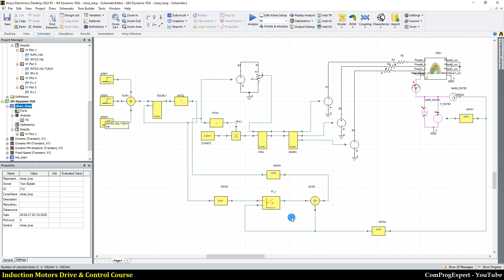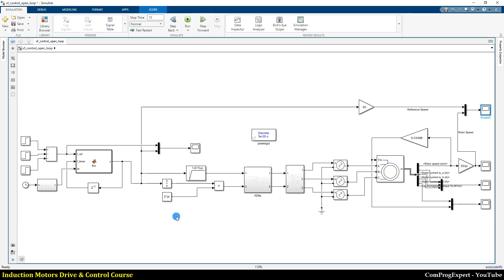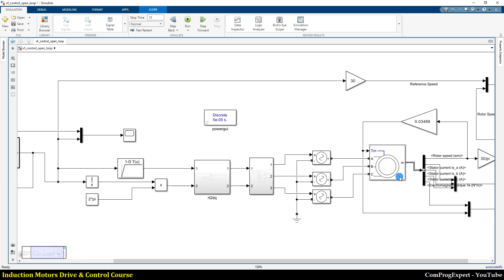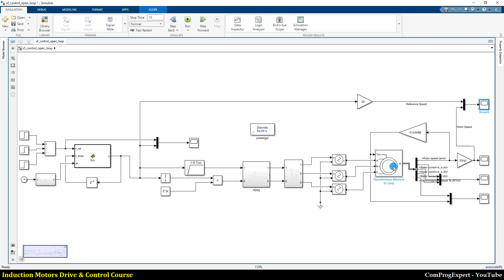We can also check the total losses of the motor. In the lumped parameter version it is complex to include the effect of iron losses or the non-uniform distribution of current in the rotor bars, but with the finite element model all of those effects are included. This is really powerful — for example, you can set parameters for maximum efficiency, which would require a very complex motor model in MATLAB.